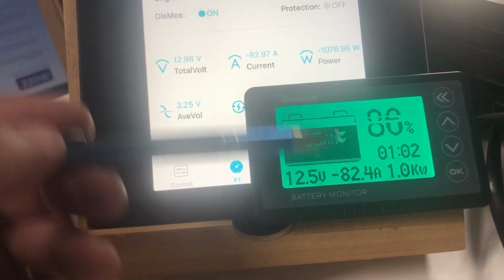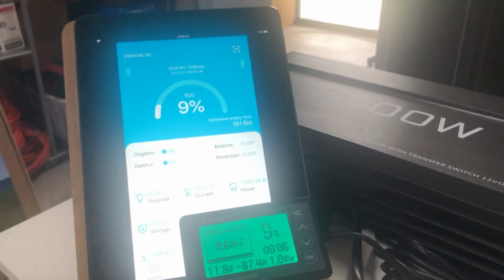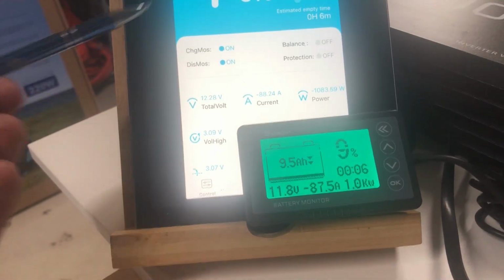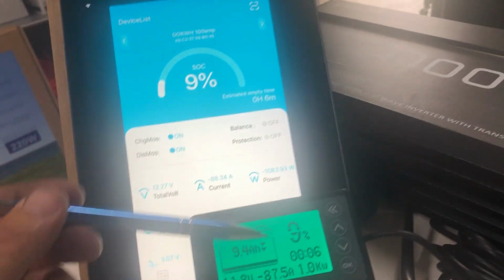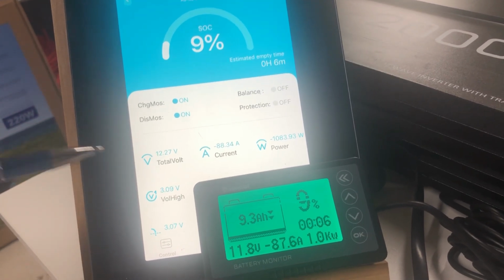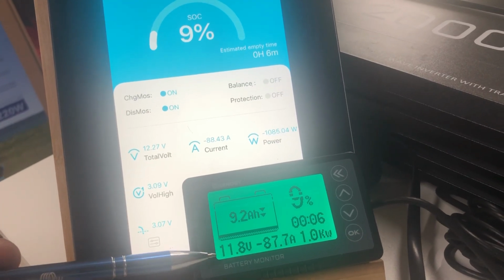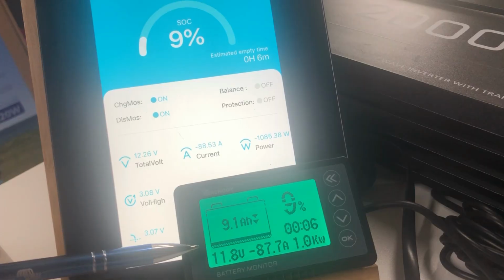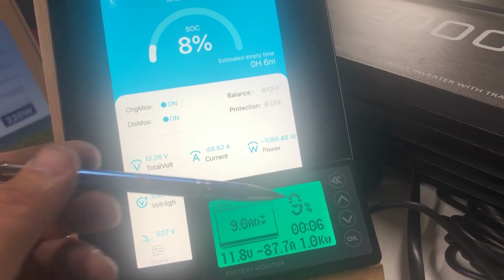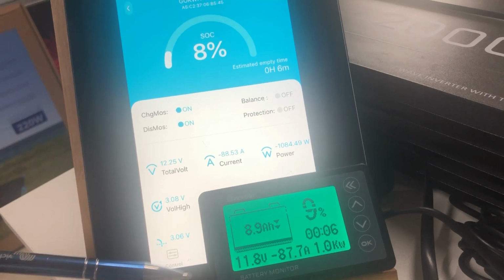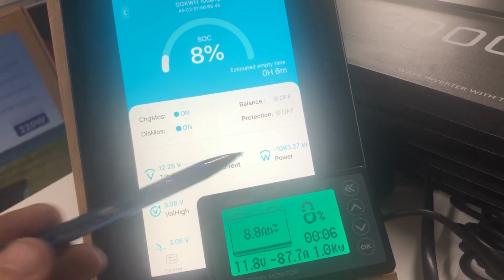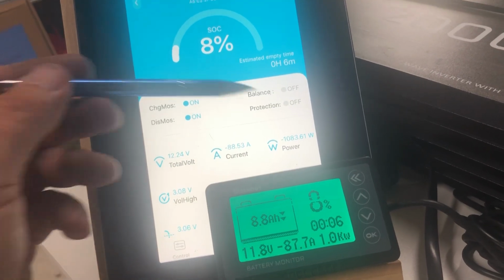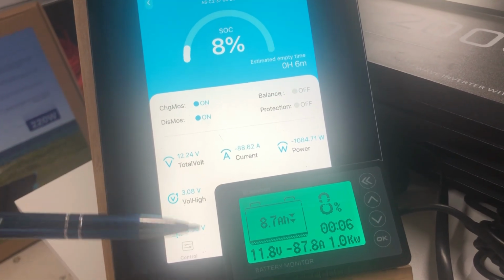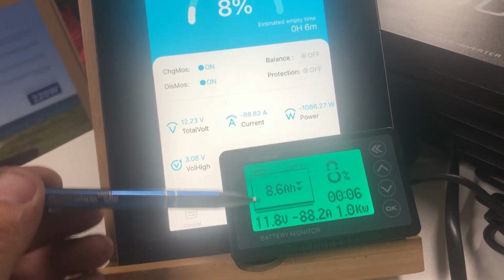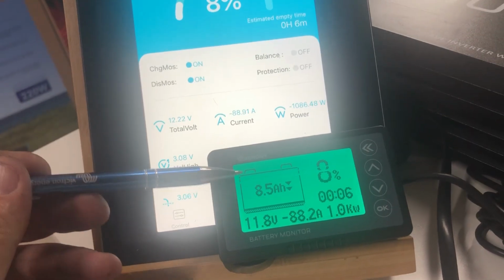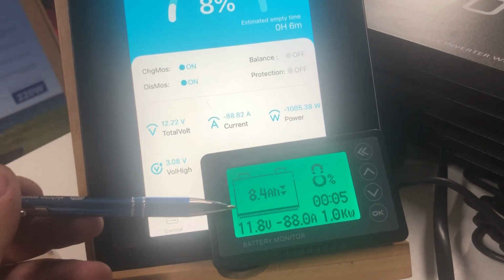But look, overall so far I'm happy. Coming to near completion at the end of this test, and as you can see, state of charge is 9% on the BMS, 9% on the monitor. We've got a little bit of deviation in voltage there, but that's voltage under load, so I'd expect that to drop. On the shunt, 9 amp hours remaining, which equals 9%. It's just switched over to 8% here. 88 amps, 87 amps, and we've still got that deviation in the watts, and they're both showing 6 minutes to go, so all good there. As expected, that gauge has come down, so that black area has gone down to near nothing, which you'd expect due to the depletion of the battery being just about done.